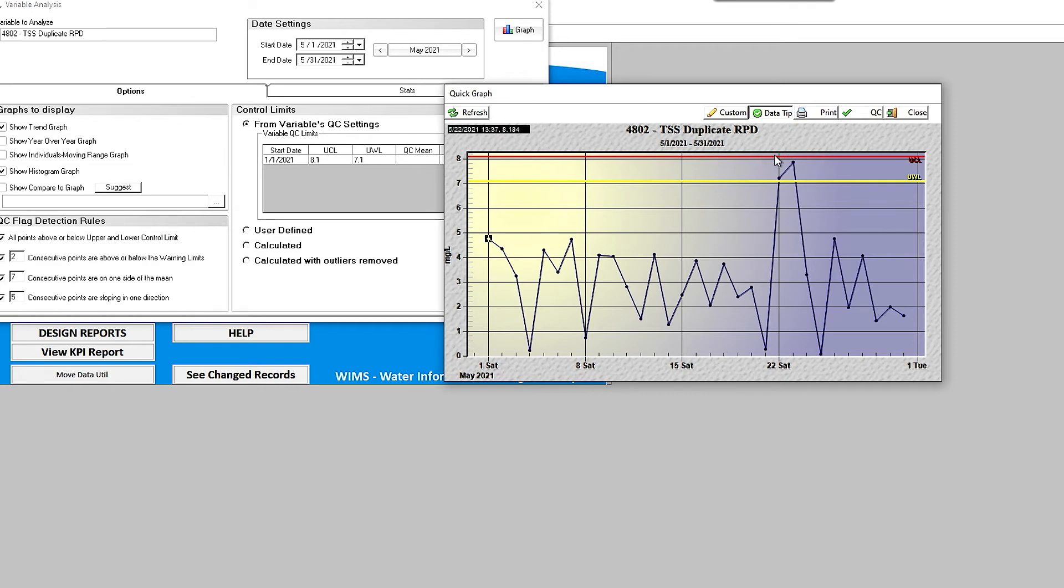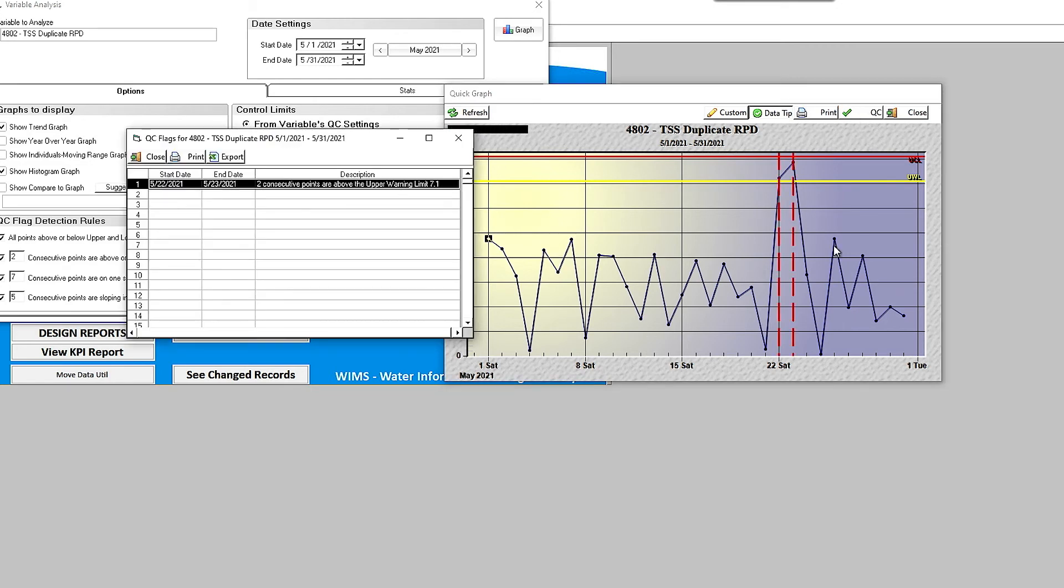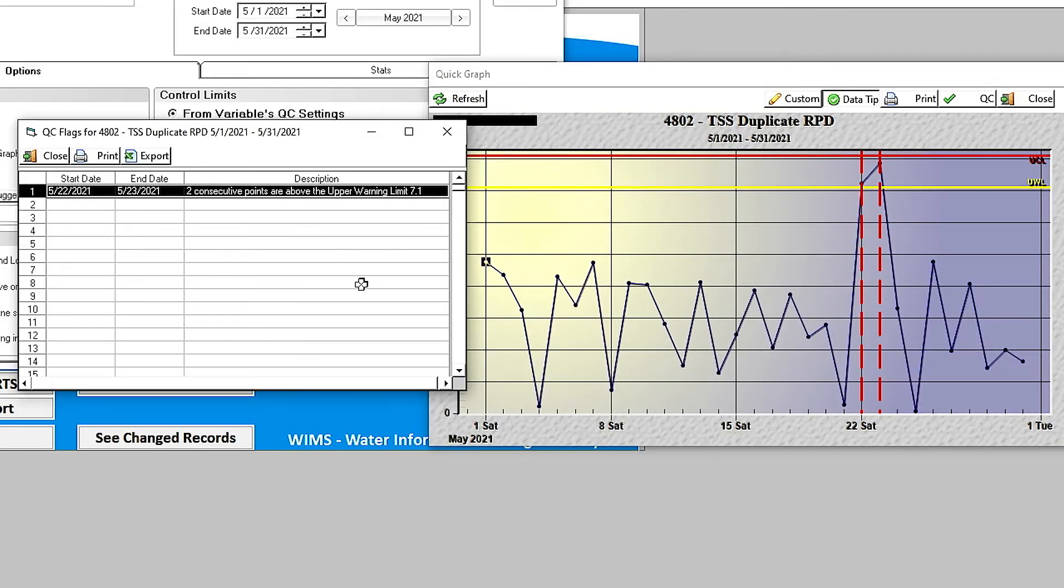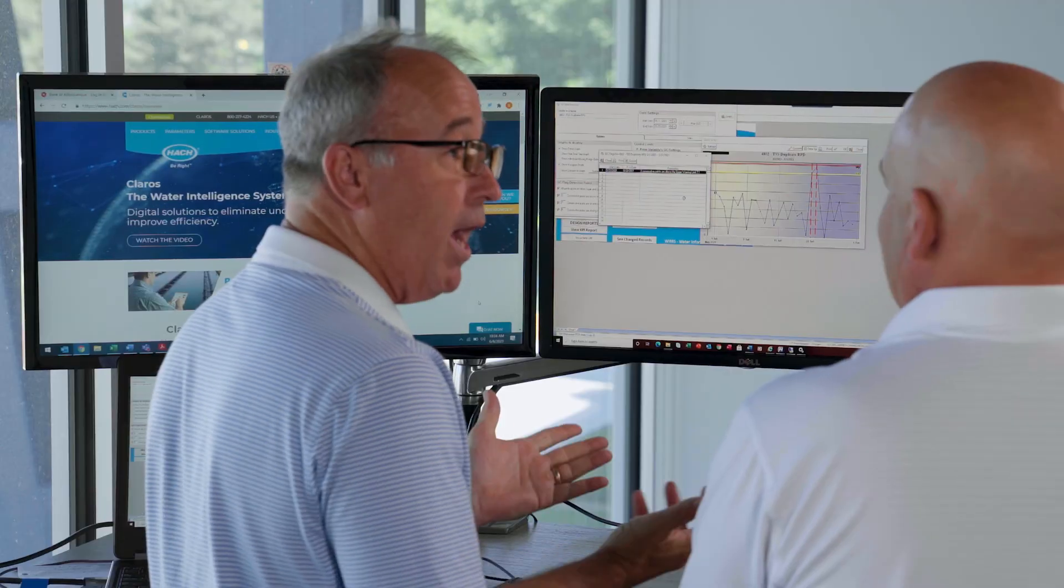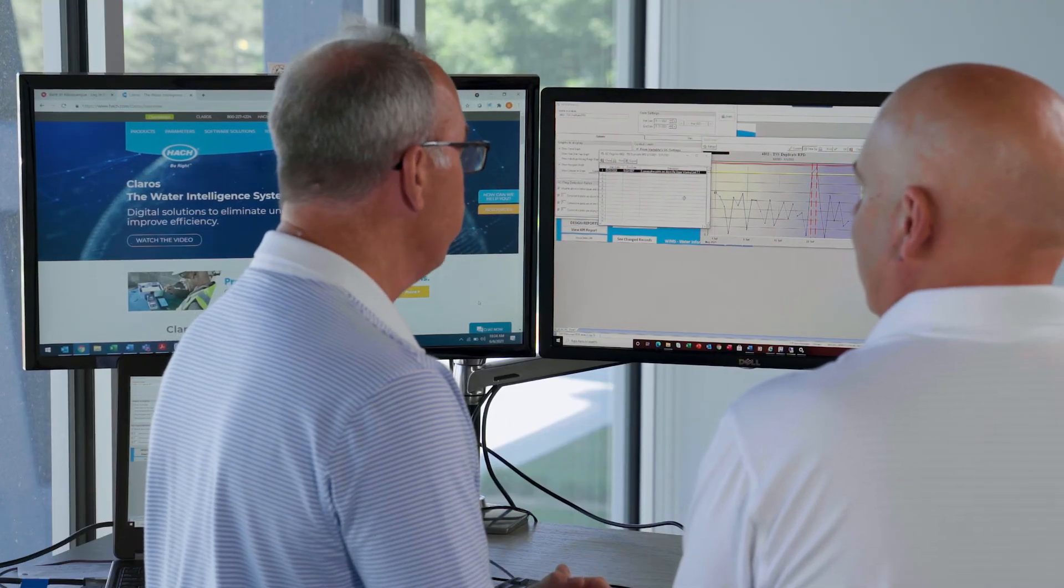So I'm a little bit more familiar with the trend graph. So that's what I have here over the last month. And I see here I've got some points that are getting close to the control limit. I can click this QC button right here. And notice it highlights these two points. And it says I've detected two consecutive points are above the warning limit. So the software can automatically apply QC rules such as five points sloping in one direction. So you're falling off a cliff maybe. Or in this case, the two consecutive points, it's pretty easy for a user or for a human to pick up, hey, that one point is above the control limit. But it's a lot more difficult to count five consecutive points and know that it's going up. And you may be in a situation where you need to look at your cleaning procedures or your lab procedures to find out why your QC is doing that. Very cool.